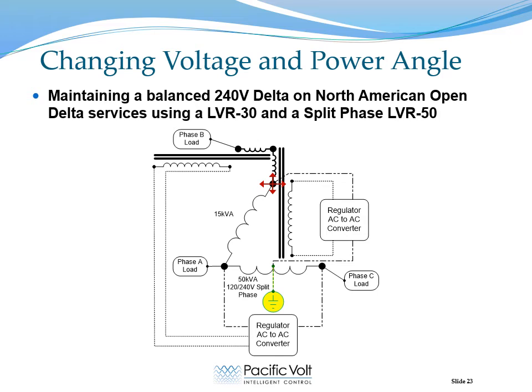Two regulators can be used to mitigate the voltage collapse on an open delta service. One regulator is typically connected to the split phase transformer, and its function is to move this point left or right. A second and significantly smaller regulator is connected between the neutral point and this point, and its function is to move that point up or down. So by coordinating the actions of these two regulators, we can move this point around in order to maintain a true equilateral triangle for delta connected loads.